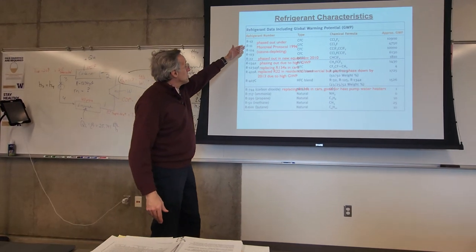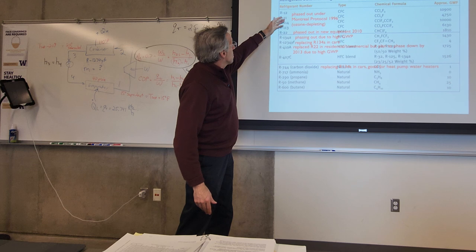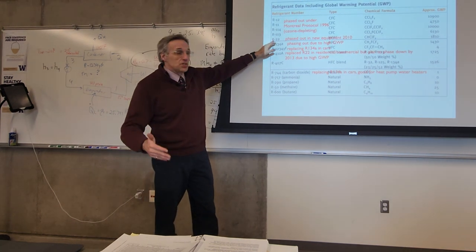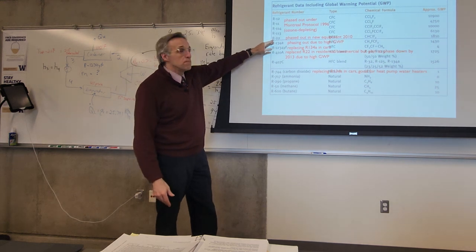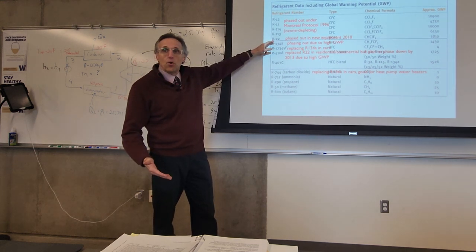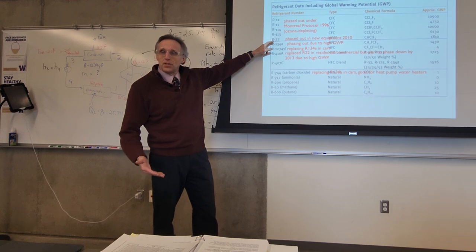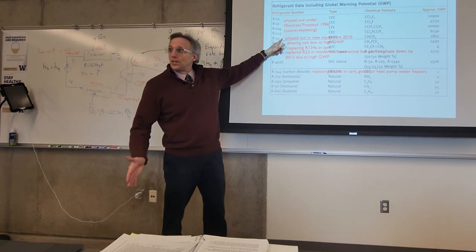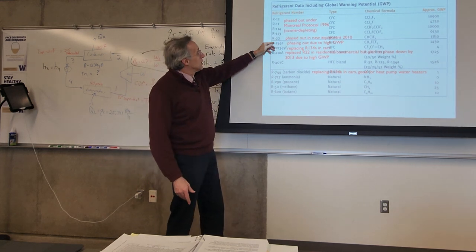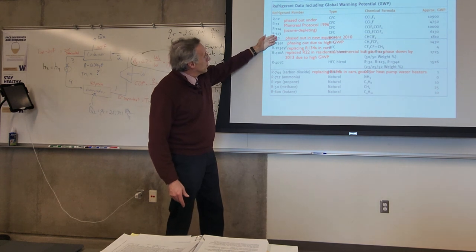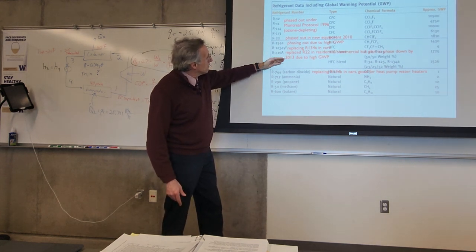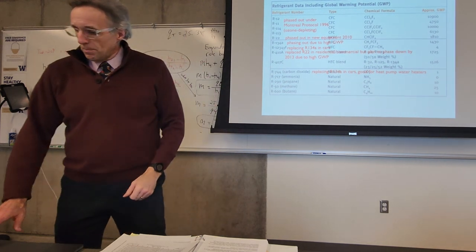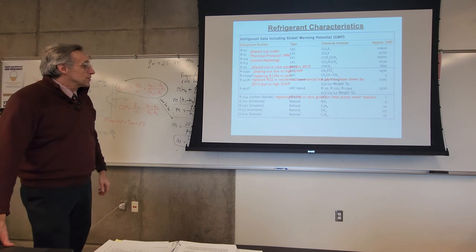If you look at them, these are phased out. R22 was phased out in new equipment in 2010, but I think you might still be able to get a hold of it, but probably not. I think in 2022 it might have been, or maybe this year, or very recently, you can't even get this for replacement anymore. And then these are the ones that are going to be going away in the next 10 years or so, and there are still a lot of questions about where we're going. With new refrigerants, this is wide open.